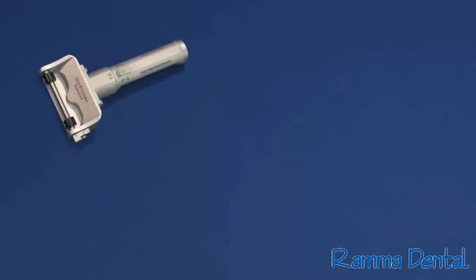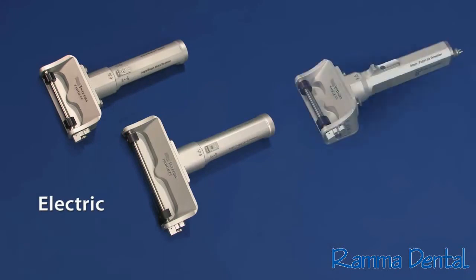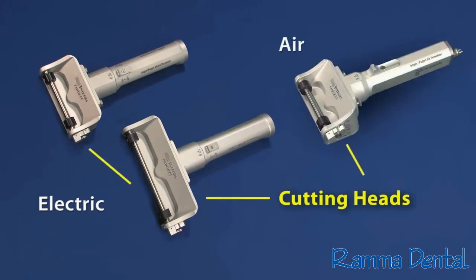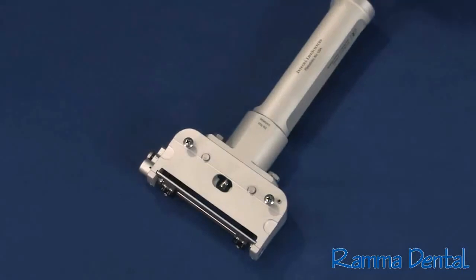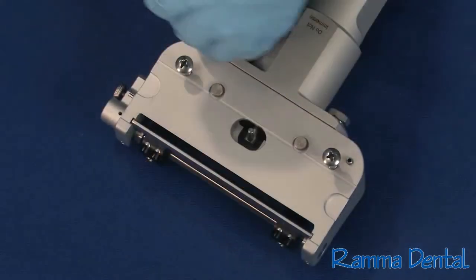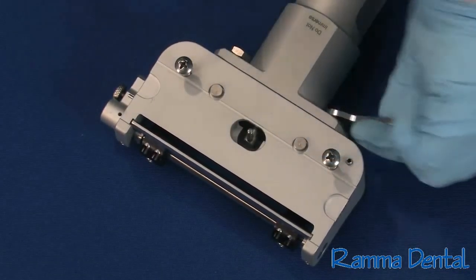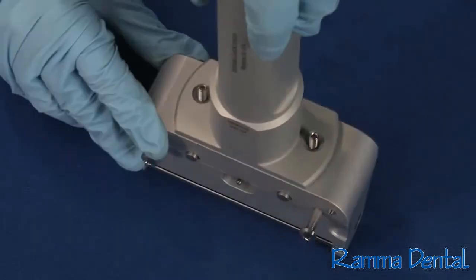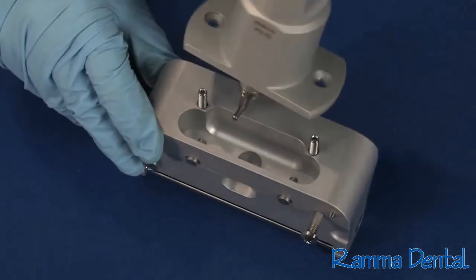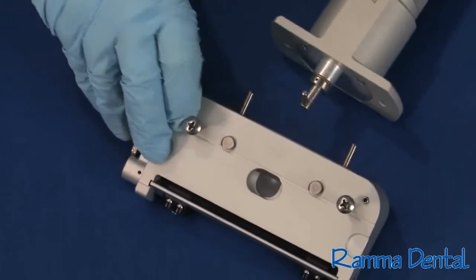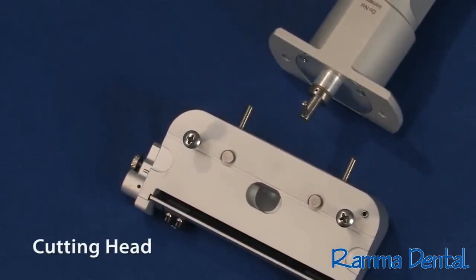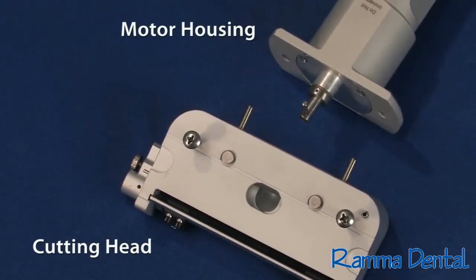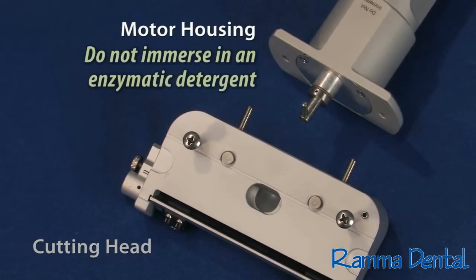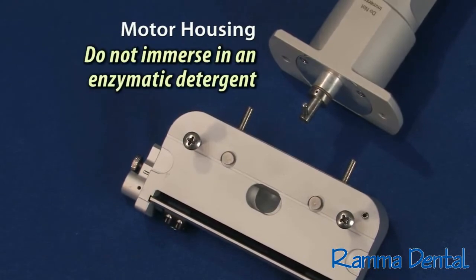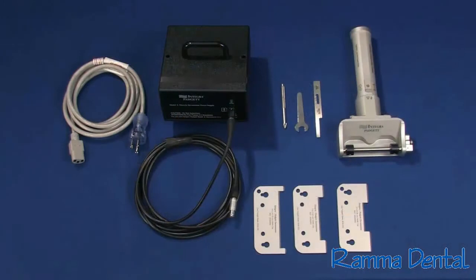The Model S, Model S6, and Model C dermatomes also feature a unique removable cutting head to allow for more thorough cleaning. The cutting head can be removed from the motor housing by loosening the nuts on the back of the head. Then simply pull the head off. This allows the cutting head to be fully immersed in an enzymatic detergent. The motor housing should be scrubbed and rinsed, but do not immerse the motor housing in an enzymatic detergent.